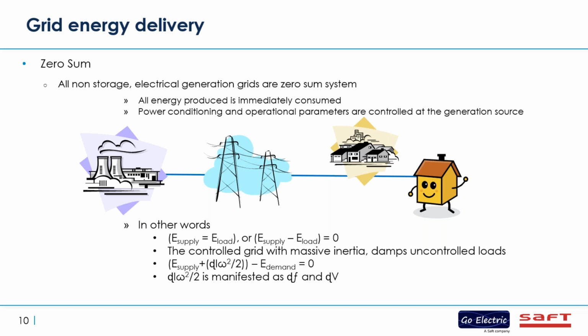The controlled grid has massive inertia, and that damps uncontrolled loads and absorbs shocks and smooths the system. Micro changes in rotational energy manifest themselves as micro changes in frequency and voltage. And those small frequency and voltage changes are instantaneous balancers, but they average out over time.